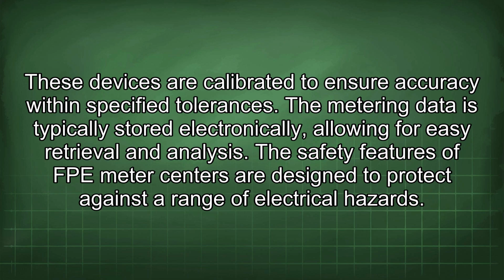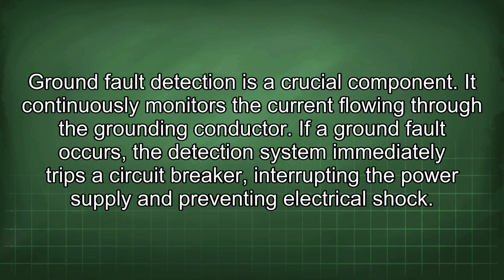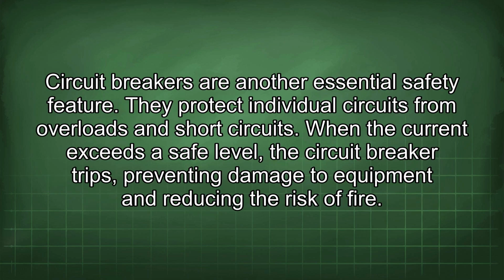The safety features of FPE meter centers are designed to protect against a range of electrical hazards. Ground fault detection is a crucial component. It continuously monitors the current flowing through the grounding conductor. If a ground fault occurs, the detection system immediately trips a circuit breaker, interrupting the power supply and preventing electrical shock. Circuit breakers are another essential safety feature.